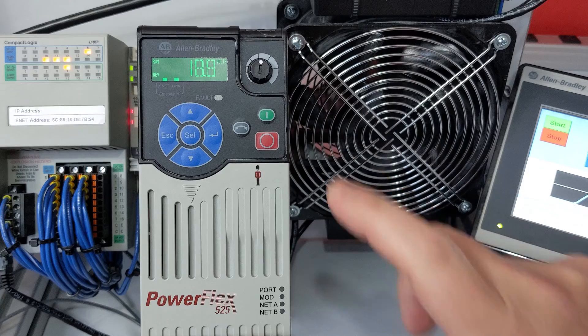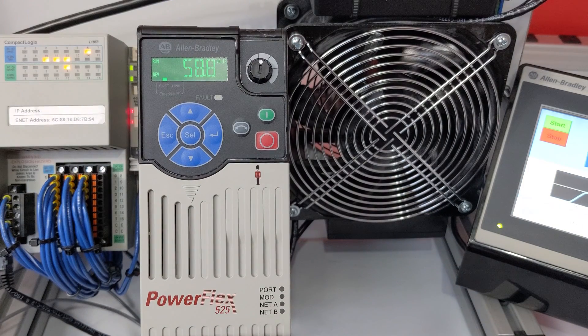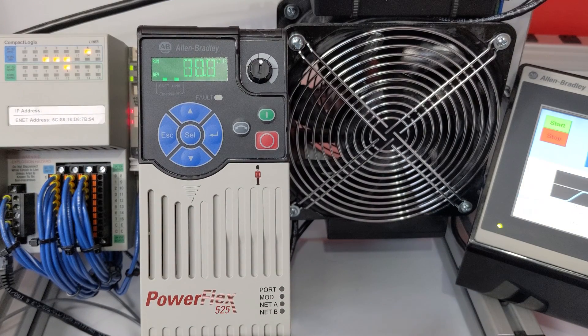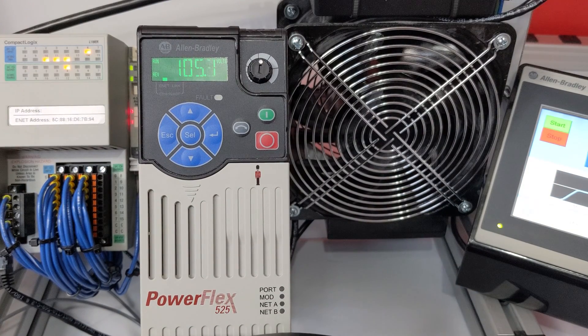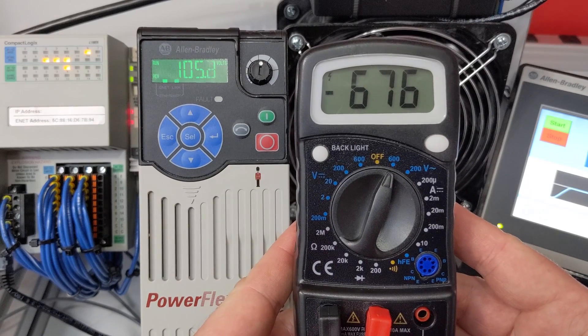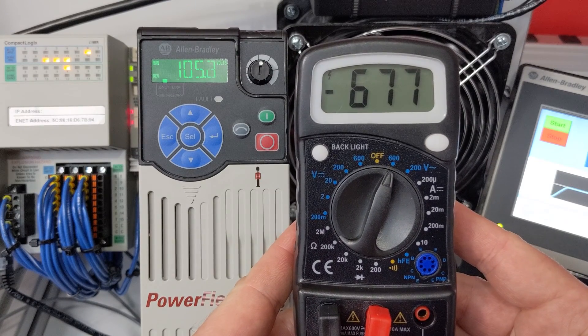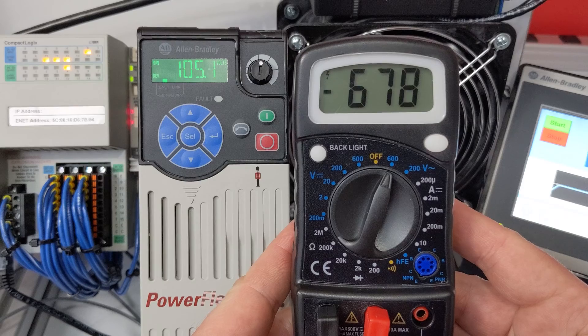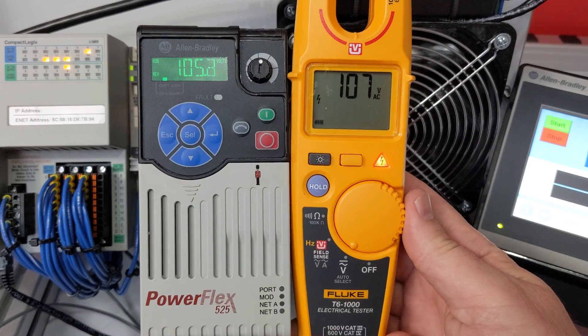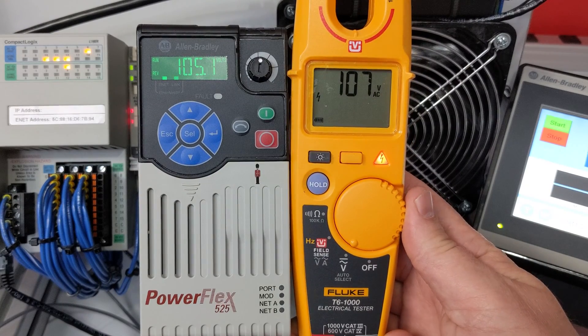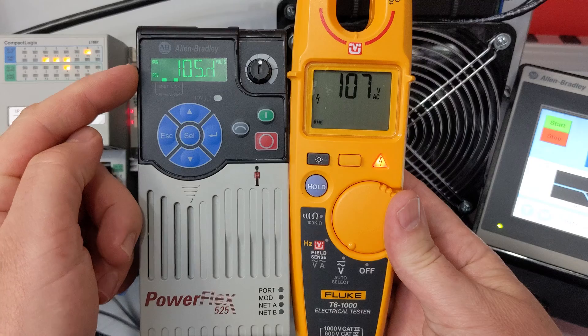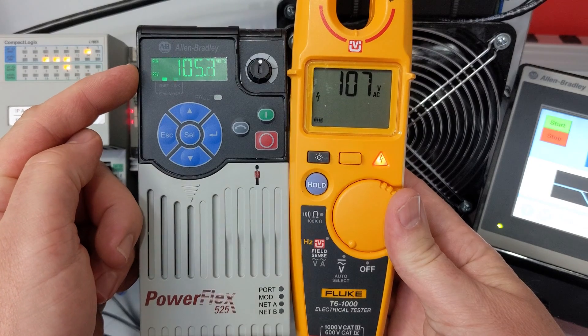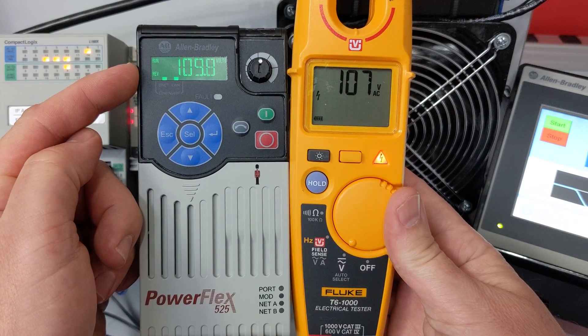I'm going to hit the green button. And the voltage is going to go up to 105 volts. And on our Brand X meter, we have 676 volts negative AC. On the T6-1000, we're showing 107 volts, which is pretty much matching what we're showing on the PowerFlex 525.